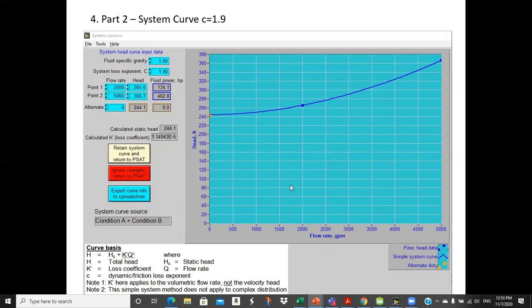Okay, then to calculate system curves, and I think we're asked to do this with two different exponents. We're asked to do it with an exponent of 1.9, and then the next slide is doing it with an exponent of 2, just to see the difference. So we had 2,000 GPM at 265.6 feet of head and 5,000 GPM at 366.7 feet of head. Okay, and so that's the fluid horsepower, by the by. But here's the static head calculation, and this is the K prime loss coefficient that goes into this equation right here. So the static head is 244.1, and this K prime is 1.14943 times 10 to the minus 5. Okay. So that's with the exponent of 1.9.